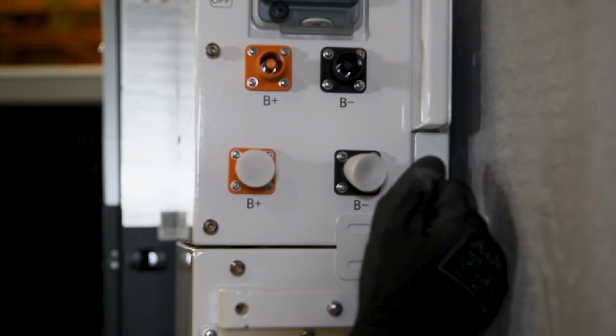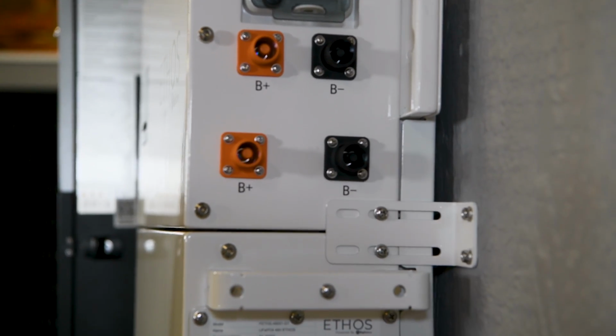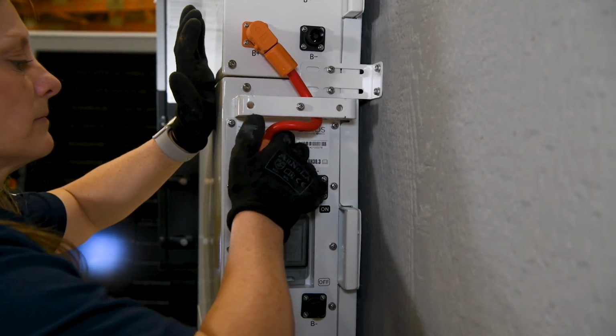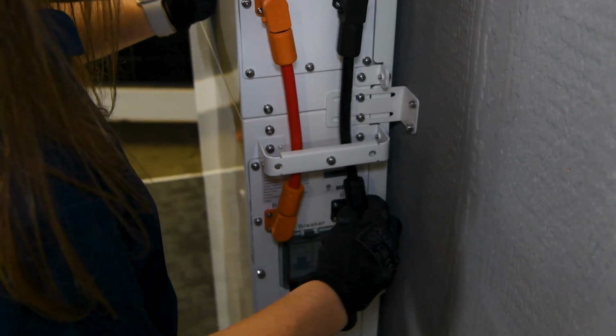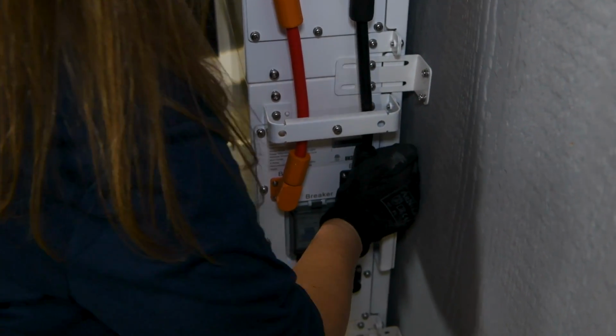We'll hold off on setting up our second stack of batteries for the moment. With our first stack now securely mounted to the wall, let's move forward with connecting our battery cables on the right-hand side. First, remove the protective caps. Start by connecting the red cables to the B positive terminals and the black cables to the B negative terminals.